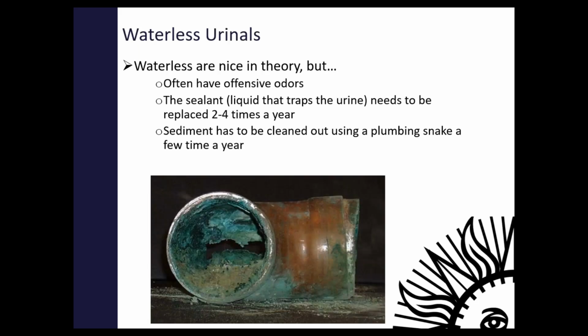So waterless urinals, again, here's what a urinal looks like if you do not take care of the piping. It starts to get a buildup of all that blue sludge, and then the urinal stops flushing, and you get a nice urine smell wafting out of your drain. So just make sure if you do recommend a urinal or waterless urinal, you recommend O&M as well. Don't just claim water savings. You're going to have to claim water savings minus your O&M practices to take care of this urinal.